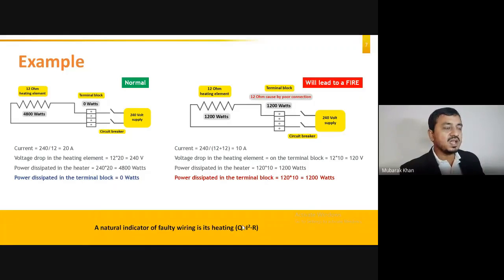Now, what if there is a loose connection at the terminal block? Here in this example we have taken a loose connection at the terminal block to be around 12 ohm, caused by poor connection.